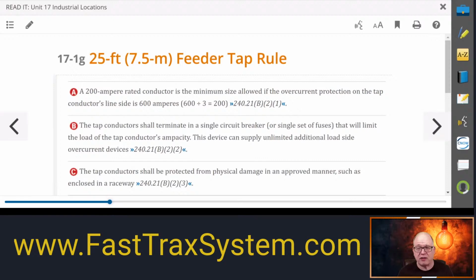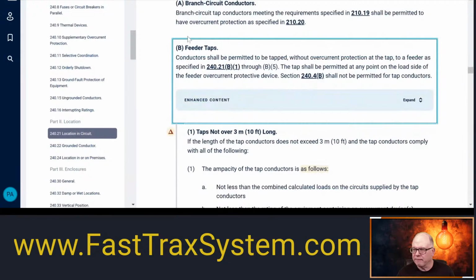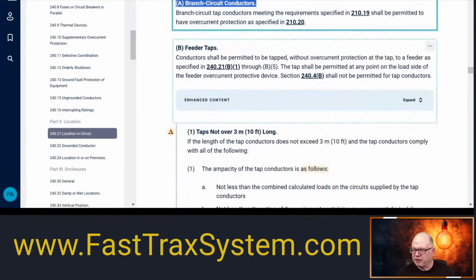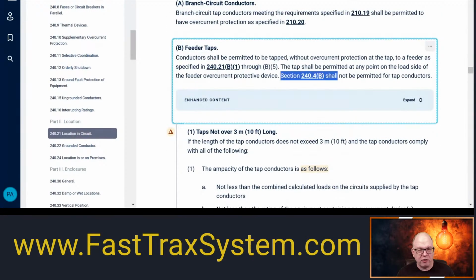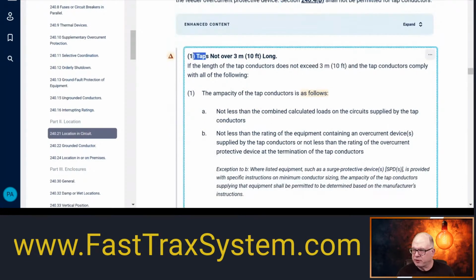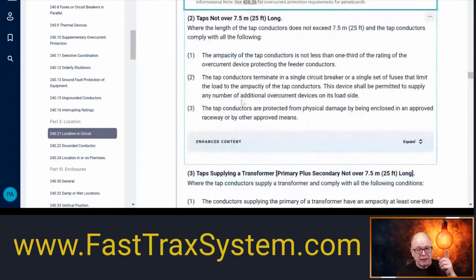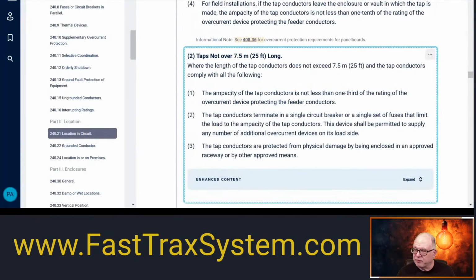Yes, under these conditions. So where are we at in the code? We're in 240.21, and we'll be looking at (B)(2). Okay, so let's make sure we get in our code book where we need to be. Here's 240.21 right here. So here's where we're at, right here. And we're going to be looking at feeder taps again. Remember, no next size up rule. Can't do that for taps. We did the 10-foot last week. Go watch that episode if you missed it. And now we're going to taps not over 25 feet long. And again, it's very short.